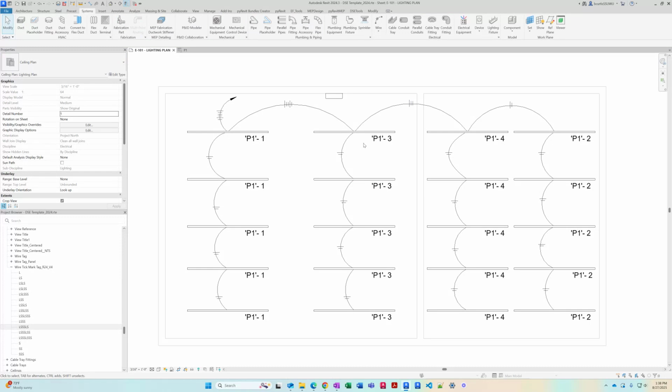So now we've got 3, 4, and 2 in this piece of wire conduit. So we would be looking at 2 shorts, 2 and 4, and then another short on a separate phase group with circuit 3. So this is actually still correct. And then we come to this final group, and now we will have circuits 1 and 3 sharing a neutral, and that means this is incorrect, and circuits 2 and 4 will share a neutral.